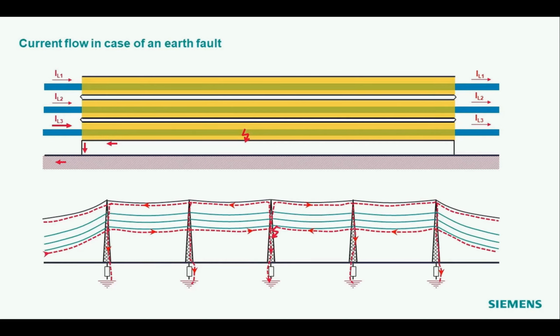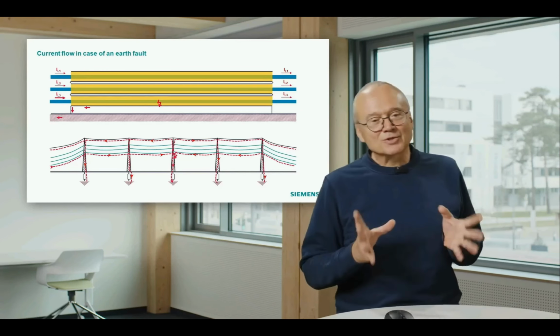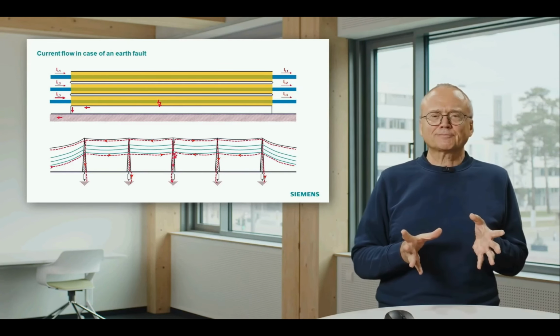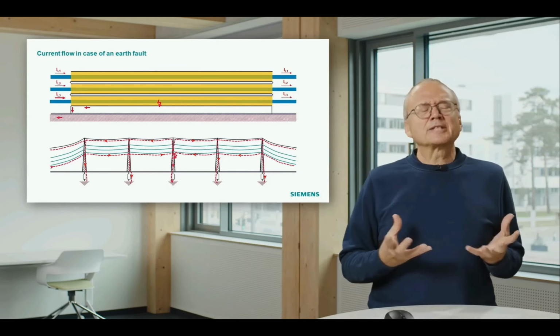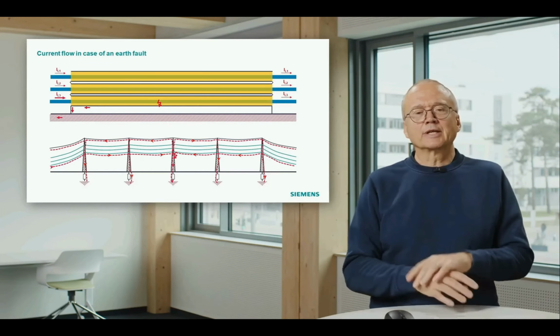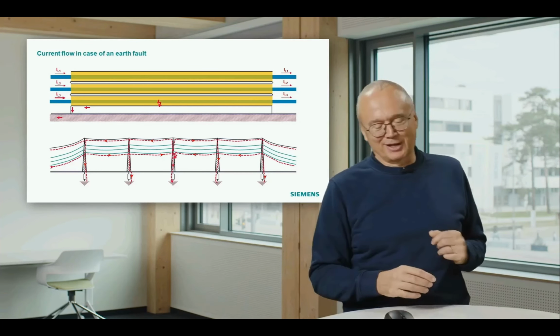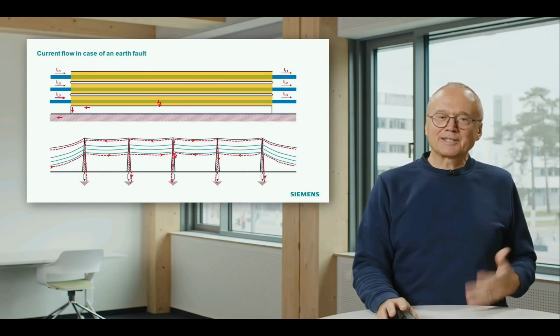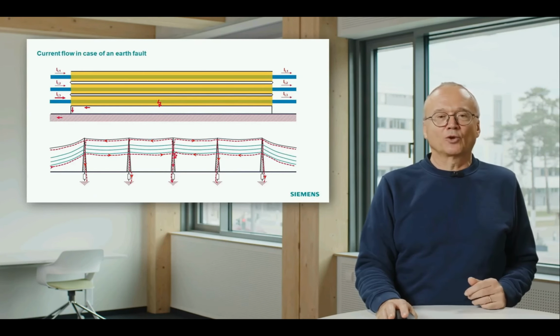That means the current comes from both sides along the line to the short circuit point, and then part of the current flows from here directly into Earth, and another part of the fault current flows along the earth wire into the grounding of other towers on both sides. That means you see here, in case of an earth fault, the earth current is a very distributed thing. There is no one location where you really can measure something, and that makes the earth current sometimes a little bit strange. But let's come back to the question, what is now the earth current in this context?